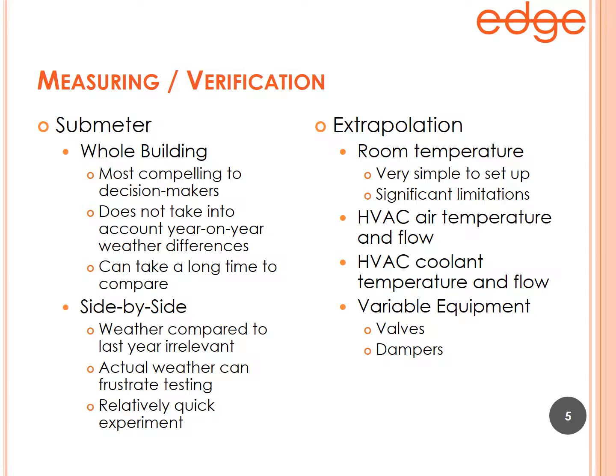Another sub-metering strategy is side by side: take two adjacent hotel rooms facing the same direction with the same load, both empty, with the same set points — one has window film, one does not. Sub-meter just the air conditioning system on each room. The biggest advantage is it makes last year's and this year's weather irrelevant, since you're comparing in real time in the same weather situation.